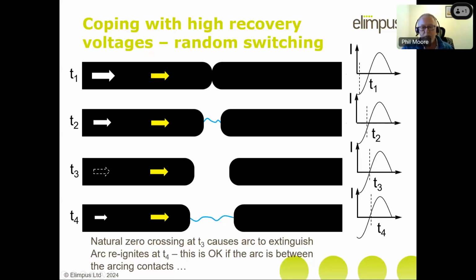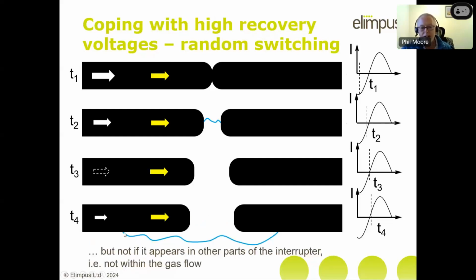And the danger with having a reignition in a circuit breaker where the contacts are reasonably well separated is that you might get this effect. You might get the arc deciding not to go through the part that you expect it to. It might go on the outside, in which case it's no longer going through the gas flow and it's no longer being controlled. If you have that situation, then you are in a very bad situation from an interrupting the shunt reactor point of view. I will show you the effect of that in some of the results that I've got when we get on to the defects section.